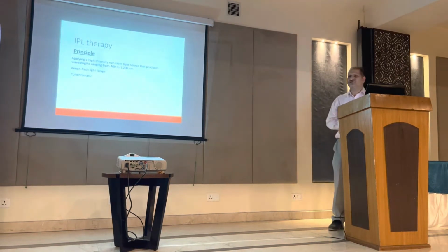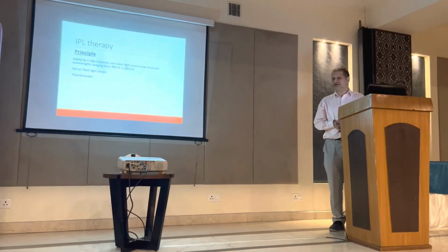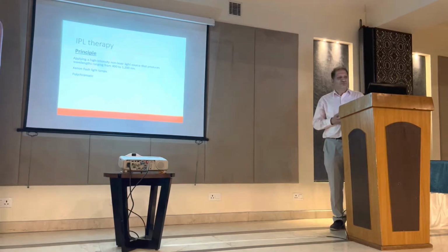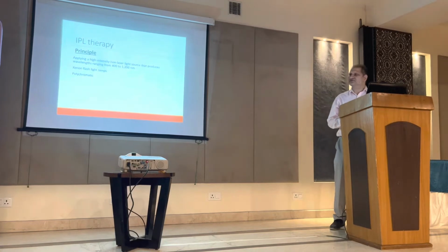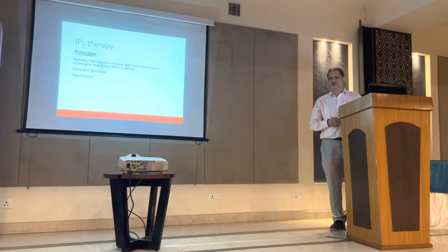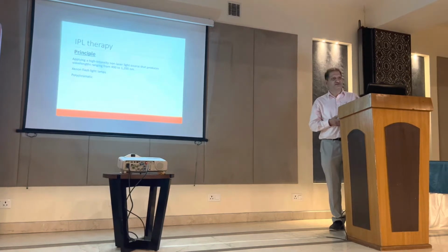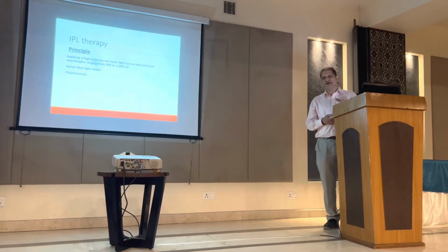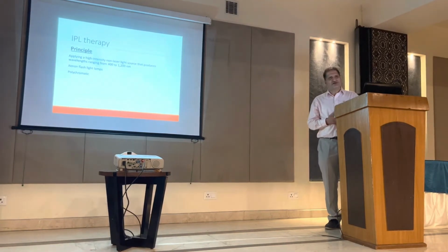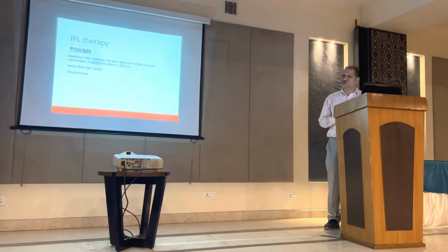IPL therapy has long been used in dermatology in rosacea, and it has also been used in acne. The principle is we use a very intense pulse light, from xenon flash lamps, which is a polychromatic light in the range of 400 to 1200 nanometers, but it is filtered and made available at 500 nm, and it is a very intense pulse light. Previously in rosacea, they used it to coagulate the vessels, and in acne, it was used to arrest bacterial growth.